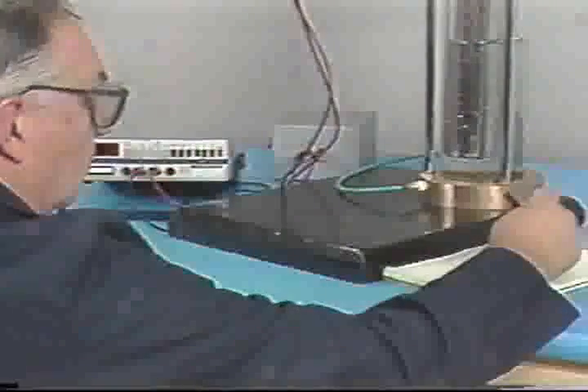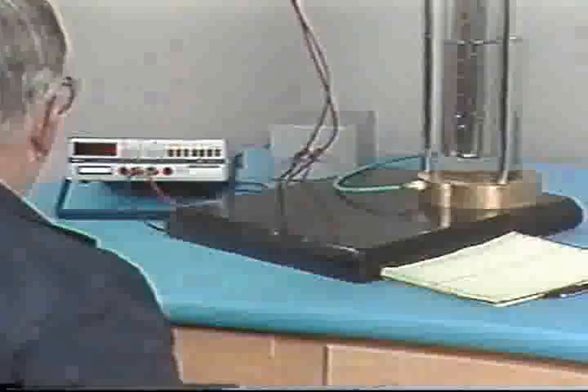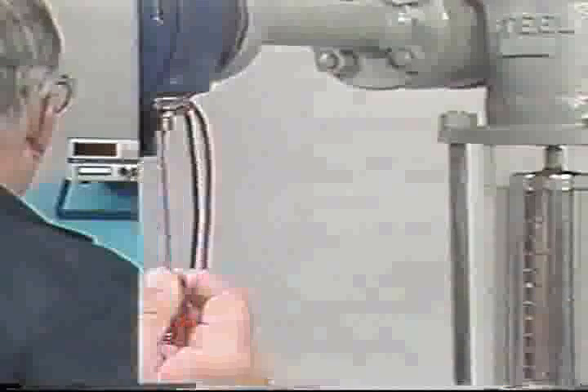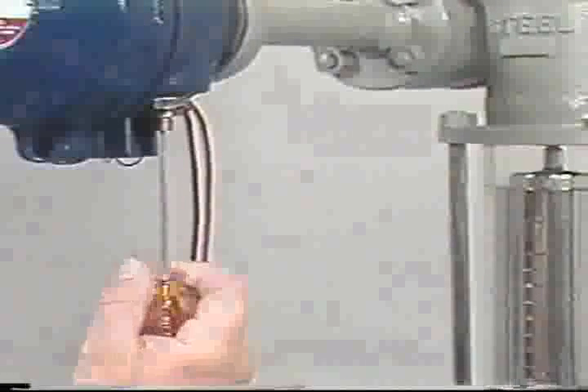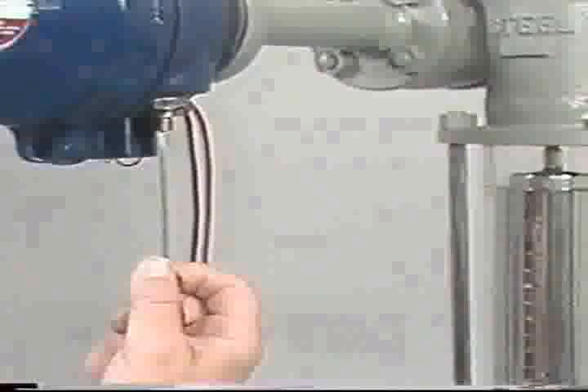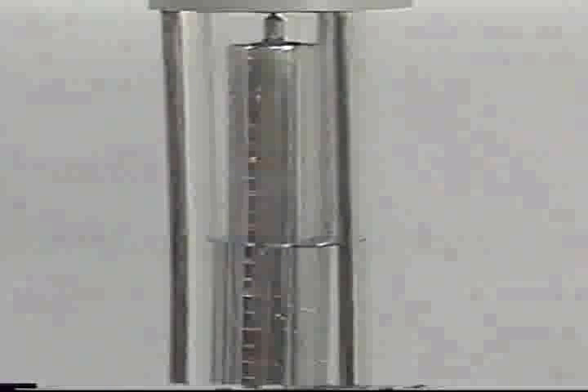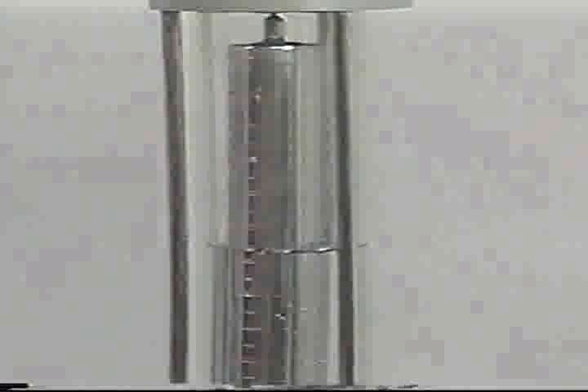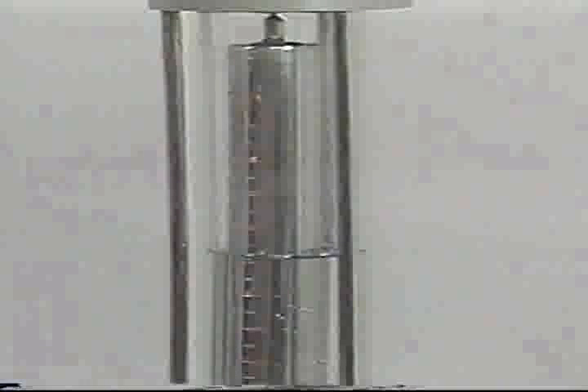If the mid-range value shows non-linearity, make another zero and span check, and adjust if necessary. Check and adjust the span again, repeating the procedure as necessary. Then, drain the chamber again to the halfway point and do a second mid-range check to verify the calibration.